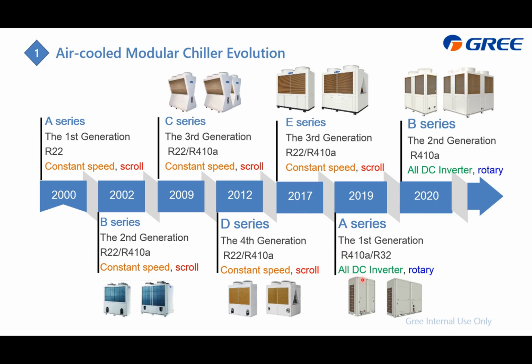It adopts the all DC inverter, which means not only the compressor but also the fan is DC inverter. Inside, the compressor changed to rotary, and it is the first to adopt R32 refrigerant. This is the first generation of the inverter, from 2019, and from 2020 it becomes this B series. The information is the same, but this is still only R410A.